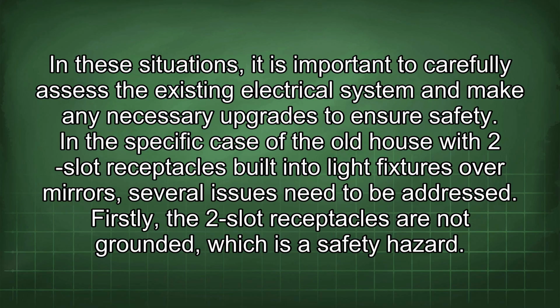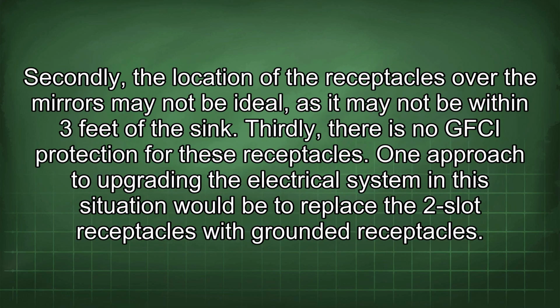In the specific case of the old house with 2 slot receptacles built into light fixtures over mirrors, several issues need to be addressed. Firstly, the 2 slot receptacles are not grounded, which is a safety hazard. Secondly, the location of the receptacles over the mirrors may not be ideal, as it may not be within 3 feet of the sink. Thirdly, there is no GFCI protection for these receptacles.